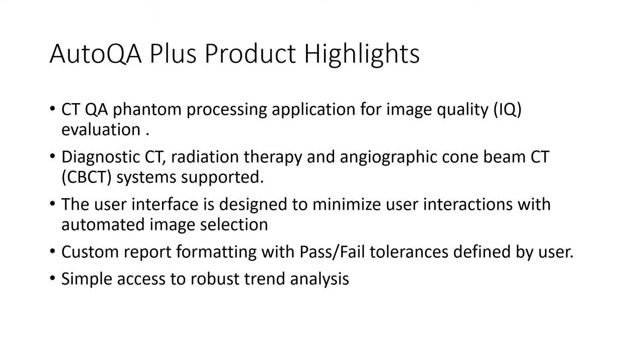We address the need of our users to customize reports with report formatting controls. These controls allow the user to select which measurements are performed, the inclusion of images, image overlays, graphs, charts, and setting site-specific pass-fail tolerances. Trend analysis, a key component for comprehensive QA, is quickly accessed through embedded links in the HTML report.